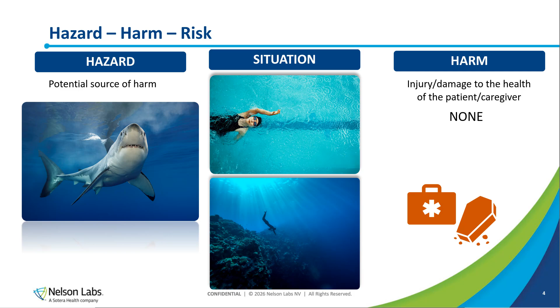But if we go back a little bit to the medical device world and the ISO 10993-1, then what we can say is that the ISO 10993-1 is also including examples of hazardous situations and of hazards that lead to harm or do not lead to harm. And so I've listed them here on this slide. So for the hazards that lead to harm, we have the presence of released harmful additives. And it's interesting here to really note the word released because it means that it's a fact and that something can reach out to the patient. We see also that there are presence of hazardous particles or potentially toxic compounds.